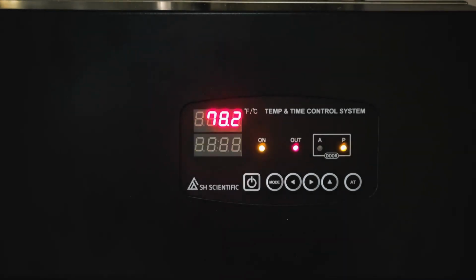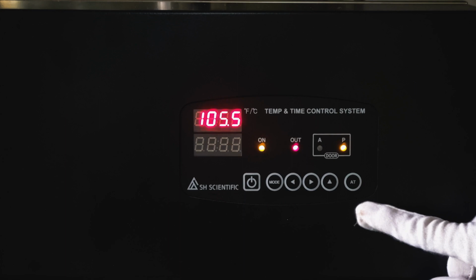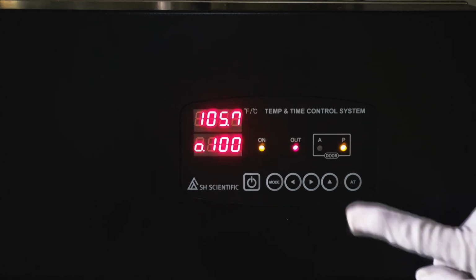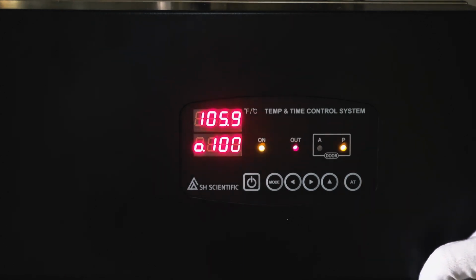On means the unit is working. Out means the heater is working. A means you can open the door, and P, for prohibited, means you should not open the door. Meanwhile, the temperature you set will keep blinking until it reaches it. You can monitor the autoclave's operating status as it runs. Press the AT button to see the ratio of heater output in percentage, and press AT again to see the time remaining in the sterilization cycle.